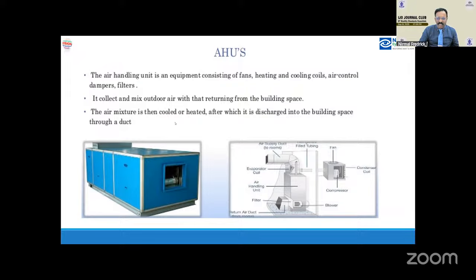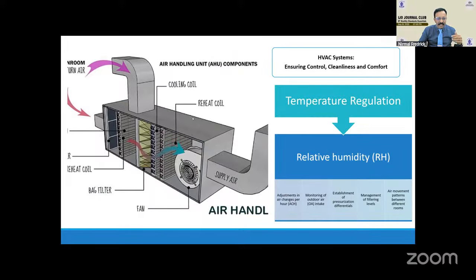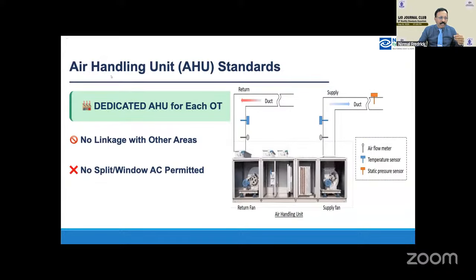And so I will not go into the fundamentals of AHU. It's basically a unit where the outdoor air is pushed into the theater through filters and through an effective heating or cooling mechanism. And this is the inside of the AHU. So this helps in two regulations. One is temperature regulation and also it regulates the relative humidity. And so NABH prescribes a dedicated AHU for each OT so that there is no mixing and no linkage with other areas, and no split or window AC is permitted.